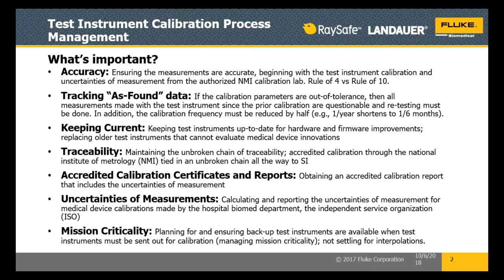Best practice also requires that you cut the calibration cycle in half. If it was once a year, it's now six months. You have to show that your test instrument remains in cal for two six-month intervals before you can go back to the one-year interval. That's the implication. It's a lot more work than just making sure you're staying in cal — nobody has time to go back and repeat work already done, whether you're in a hospital or a manufacturing company. So we're better off to keep it in cal and follow the frequency of inspection.